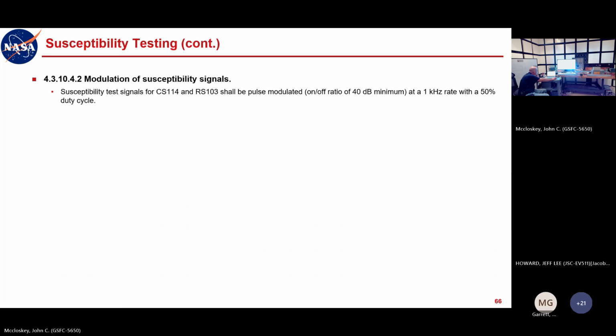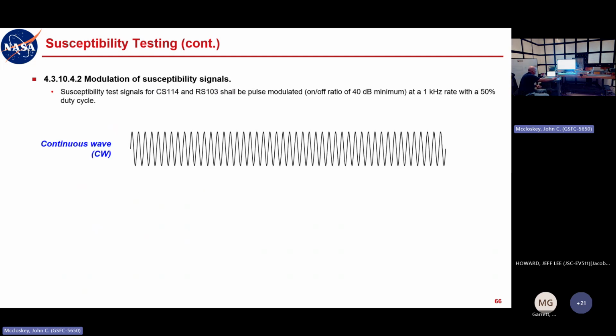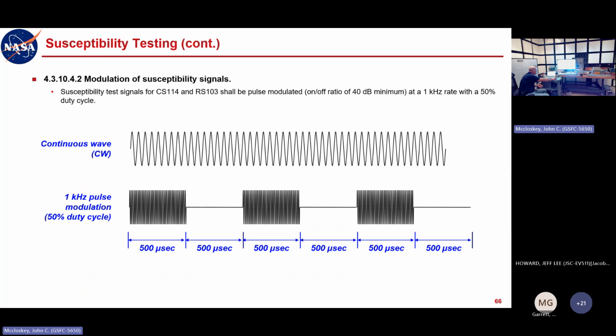A little bit about modulation. The MIL standard specifies 1 kilohertz pulse modulation, 50% duty cycle. Another bit of terminology for you is a straight up continuous wave. A sinusoid is called a continuous wave or CW signal, so you'll hear that term. That's what it means, it's just a straight up sinusoid. And pulse modulated, I've compressed the scale a little bit here, but it means that with a 1 kilohertz period and a 50% duty cycle, you're on for 500 microseconds and off for 500 microseconds.